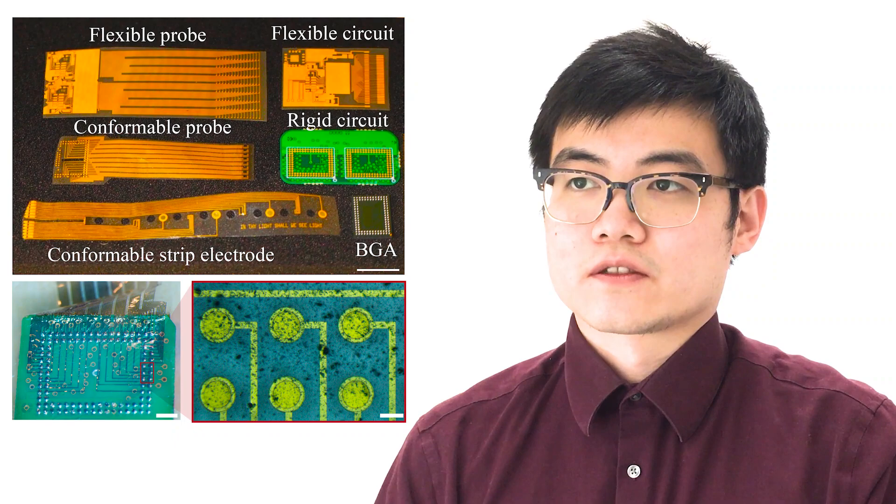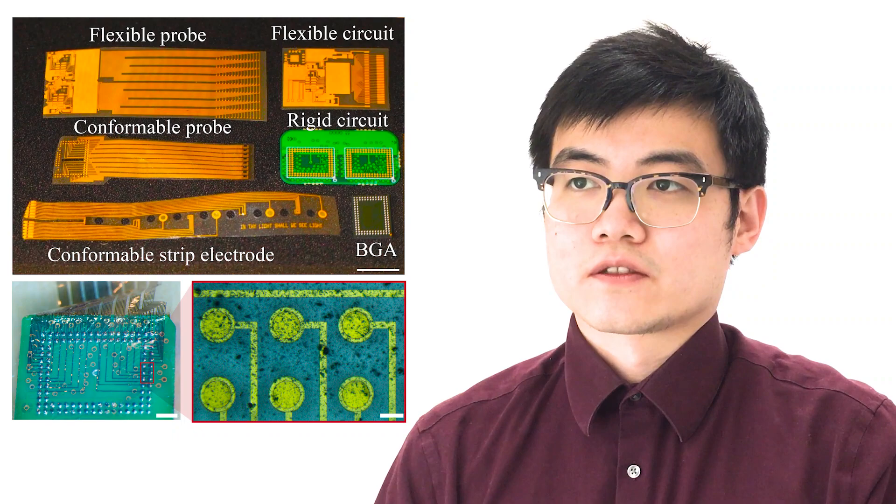MCP created an anisotropic interface that could bond conformable, flexible, rigid neural probes and electronic circuits together, permitting higher density connectivity compared to traditional connector or bonding processes.